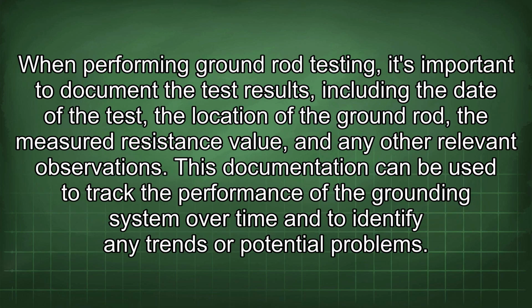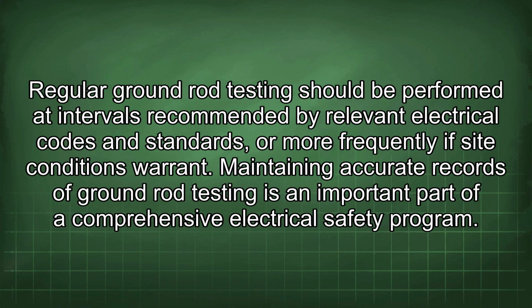When performing ground rod testing, it's important to document the test results, including the date of the test, the location of the ground rod, the measured resistance value, and any other relevant observations. This documentation can be used to track the performance of the grounding system over time and to identify any trends or potential problems. Regular ground rod testing should be performed at intervals recommended by relevant electrical codes and standards, or more frequently if site conditions warrant.